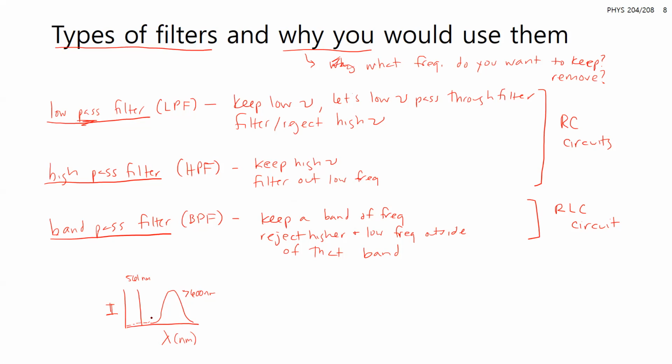I only want to be looking at this spectrum of emission in my sample. So I use a filter where, on this axis with this dashed line, this is the percent transmission of the light. I keep longer wavelengths and I reject shorter wavelengths here. So 100% transmission of this red light, while 0% transmission of the green laser light. This is called a long pass filter, because these are longer wavelengths.